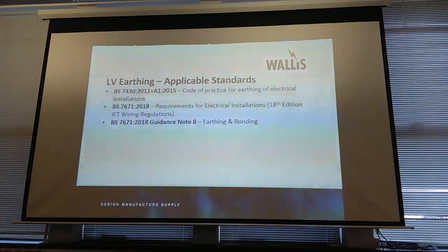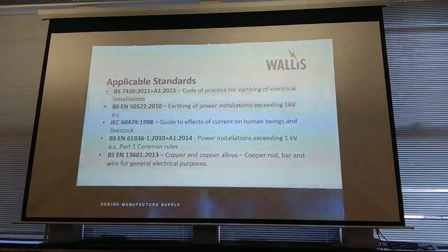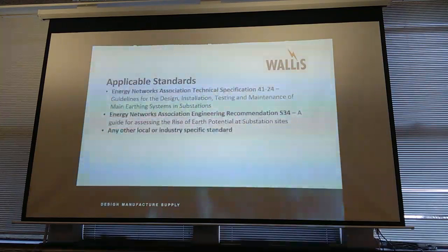Right, so applicable standards. Again, you guys will know most of those. LV is one thing, HV is more. There are a lot of standards covering HV, let's put it that way. There are the British standards, there are IEC standards, there's EN standards. You then get into the Energy Networks Association standards, which is the umbrella body for Western Power, UK Power Networks, Northern Power Grid. So you might have to work to these. And then you also have the DNO standards to work to as well, depending on where your system is connecting into the existing network. It's not as simple as they all tally together. They all tell you something slightly different. So you have to work to the most onerous standard.